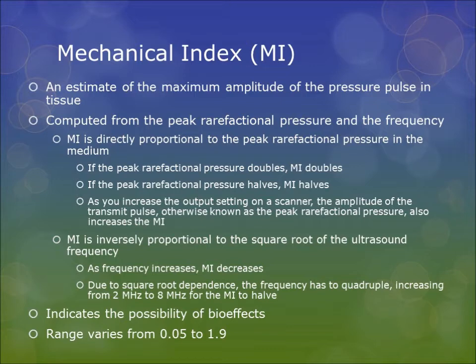MI is also inversely proportional to the square root of the ultrasound frequency. As frequency increases, MI decreases. Due to square root dependence, the frequency has to quadruple — increasing from 2 MHz to 8 MHz — for the MI to halve. MI also indicates the possibility of bio effects and ranges from 0.05 to 1.9.